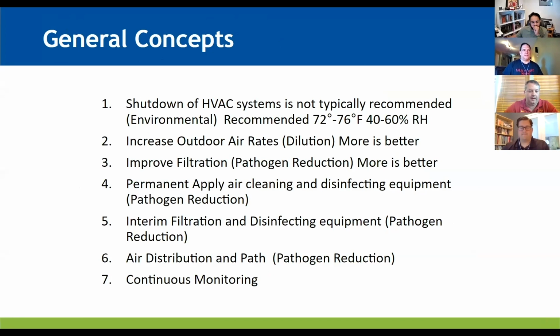Shutdown of HVAC systems is typically not recommended during the day - don't turn them off. Recommended temperature range is 72 to 76, and again that 40 to 60% relative humidity, which we'll talk about later. Increase outside air dilution - more is better. Improve filtration - more is better, generally on the order of MERV 13.